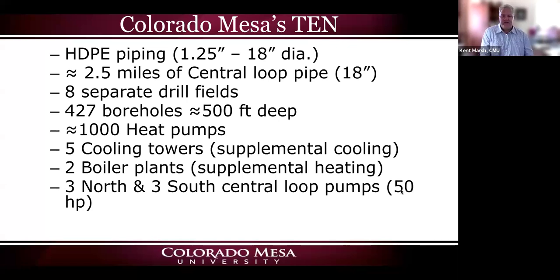So the large pipe that moves energy from the south end of our campus to the north end of our campus is actually 18 inches in diameter. We have a little over 2.5 miles of that central loop pipe on campus. Our campus is about 144 acres. We had 8 separate drill fields, but we just drilled a brand new one this summer, so we actually have 9. We had 427 boreholes, but I added 60 more, so we're just under 500. And this summer, we were actually able to dig those holes down to 600 feet. Technology has improved, and so we got another 100 feet out of each one of those holes.